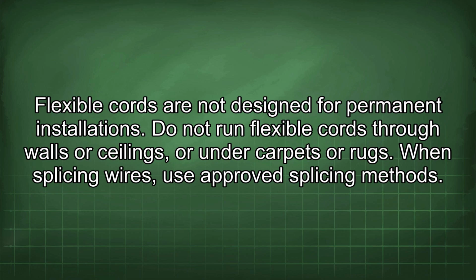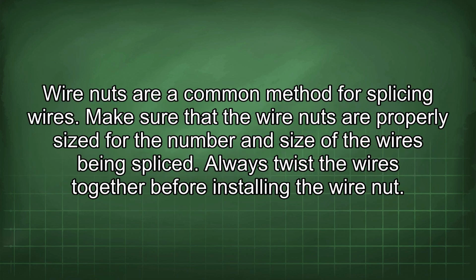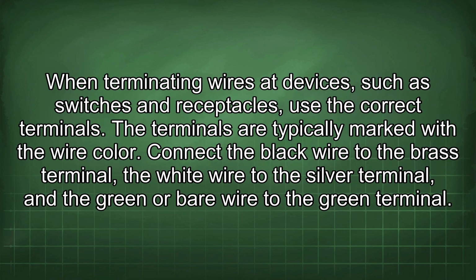When splicing wires, use approved splicing methods. Wire nuts are a common method for splicing wires. Make sure that the wire nuts are properly sized for the number and size of the wires being spliced. Always twist the wires together before installing the wire nut. When terminating wires at devices, such as switches and receptacles, use the correct terminals. The terminals are typically marked with the wire color. Connect the black wire to the brass terminal, the white wire to the silver terminal, and the green or bare wire to the green terminal.